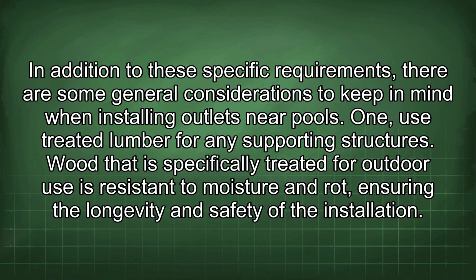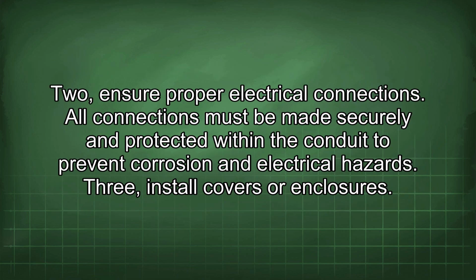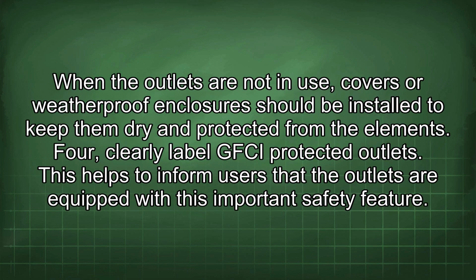2. Ensure proper electrical connections. All connections must be made securely and protected within the conduit to prevent corrosion and electrical hazards. 3. Install covers or enclosures. When the outlets are not in use, covers or weatherproof enclosures should be installed to keep them dry and protected from the elements. 4. Clearly label GFCI protected outlets. This helps to inform users that the outlets are equipped with this important safety feature.